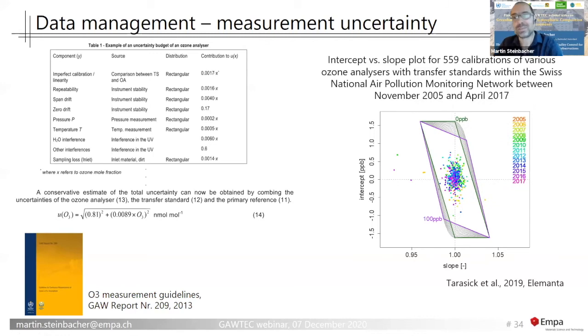And luckily we could also prove that with some experimental data. This is again from the Swiss National Air Pollution Monitoring Network that I mentioned before. Here we see the intercept versus slope. You can imagine that we make scatter plots of the measured values versus the assigned values, and then you get some intercept-slope pairs, and you apply the equation we can see on the left. All data, or 95% of the data, should lie within this gray shaded area. And there we see that this was very well confirmed by real measurements, real calibrations, so the estimated uncertainty we determined in that report definitely makes sense.